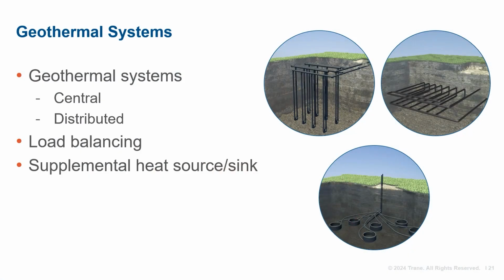Additionally, annual load profile analysis is required to determine whether supplemental heat adders or subtractors are required. We're seeing designers choose to apply air-to-water heat pumps to add or remove heat from the geothermal well field as an electrified option. Space and cost also come into play. Greenfield sites with ample space may be amenable to a geothermal well field if the funds are available. Let's look at one more option.